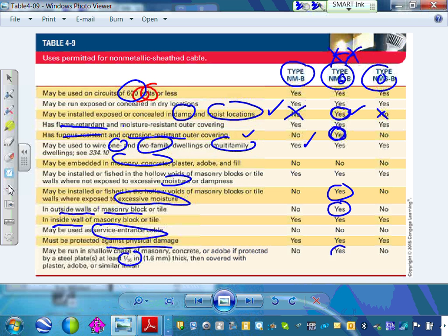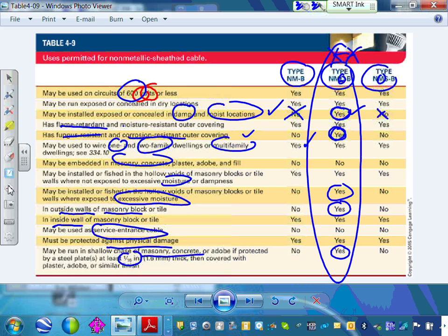So this is yes, and why not? Because of masonry. So you can put them in masonry, guys, and cover it, 116. But can you see this one stands out as a damp and excessive moisture cable? But this one, 90% of your wiring is going to be with this one. That other one will be only for probably 10% of your wiring.